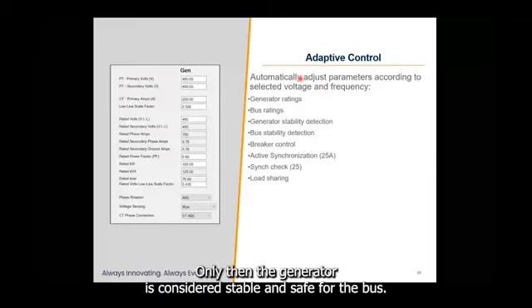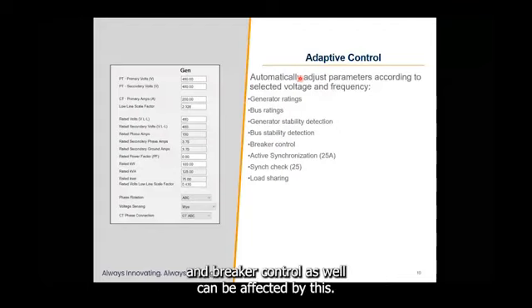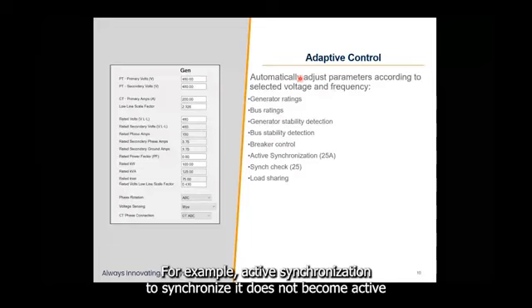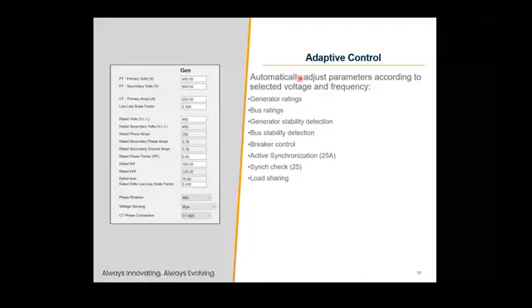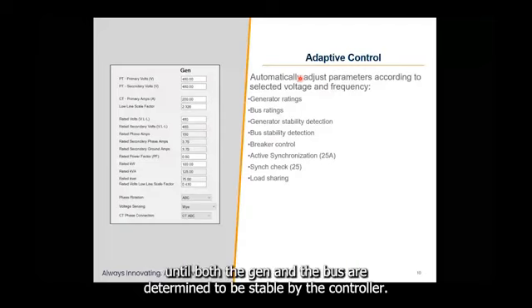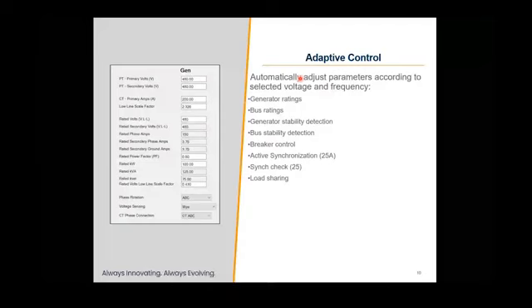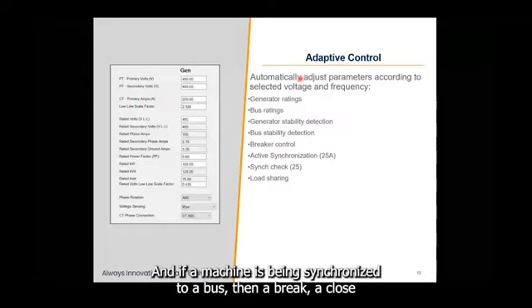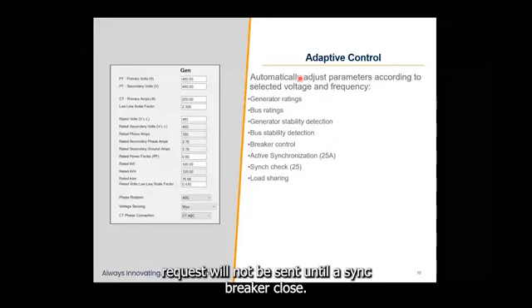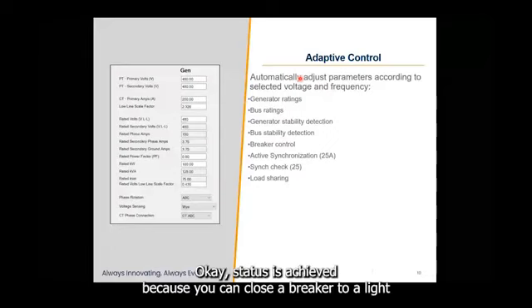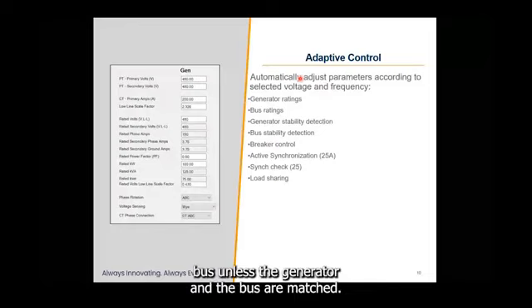Only then the generator is considered stable, and same for the bus. It must be somewhere close to its rated voltage and frequency. And breaker control as well can be affected by this. For example, active synchronization. The synchronizer does not become active until both the gen and the bus are determined to be stable by the controller. And if a machine is being synchronized to a bus, then a breaker close request will not be sent until a sync breaker close OK status is achieved, because you can't close a breaker to a live bus unless the generator and the bus are matched, right?